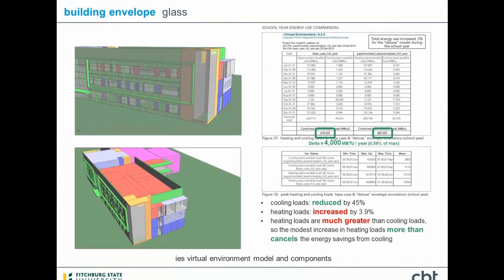On this side of the chart, we were generating for the typical low E, and on the right, the higher shading coefficient glass. And we did see a dramatic reduction in the cooling loads. We were able to drop it by 45%. On the heating side, we actually found that we increased the heating loads by 3.9% in the winter, where that solar gain is actually a benefit to the space. As you recall from a previous slide, the heating loads are dominant when taken on the aggregate over the year in this building. So in our case, the modest increase in heating loads more than canceled out the energy savings that we got on the cooling side.